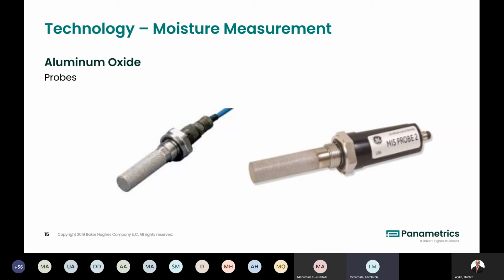So the sensor gets sent back to us, we calibrate it, and then the customer gets it back and starts thinking, oh, hang on, there's a problem with the calibration because my reading is wetter than when I sent it in. But the reason it's reading wetter is because that's the actual moisture concentration. The sensor has been drifting drier over time. So once you recalibrate it and put it back in, it reads a little bit wetter.